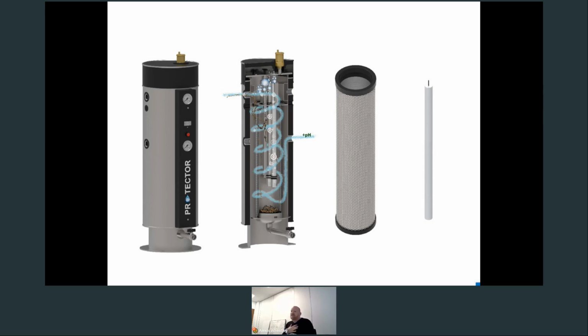This then gets released through the AAV, and then the non-magnetite particulate in that water is forced out because of the pressure it's under. That hits the 40 micron basket that we have in that unit, and then slides down to the bottom, ready to be blown down as part of the normal ppms that you would have with our units. So that 40 micron basket offers a number of advantages. Obviously the higher speed assists with that particulate, which on a wider body system, if it were travelling faster, would just push out the outlet, and so it would take longer to clean through that system.